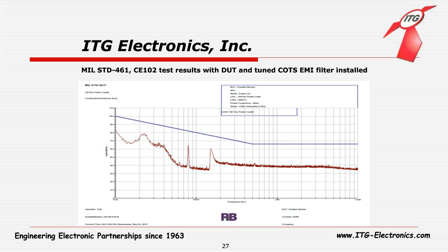But one thing that can be tried is adding a common mode coil at the output side of the filter. This way you will know the effect of it. Once you have all the components selected to pass the EMI test, then you have to go back to the filter company and ask them to make a new filter with those components added inside the filter. And Amy is right. If it's a potted unit, you can't do anything internally. All you can do is add external components.